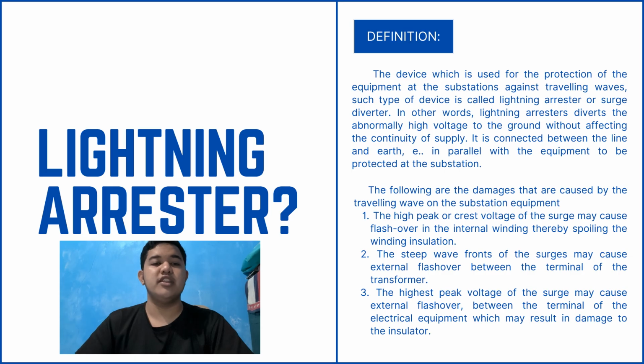Also, here are the damages caused by traveling waves. Now, what happens if there's no lightning arrestor? These traveling waves can cause serious damage such as flashover inside transformer windings, ruining their insulation; external flashover between transformer terminals, like a mini lightning bolt jumping across components; and even damage to insulators due to extremely high voltage peaks. In short, one lightning surge can cause thousands or even millions in equipment loss.